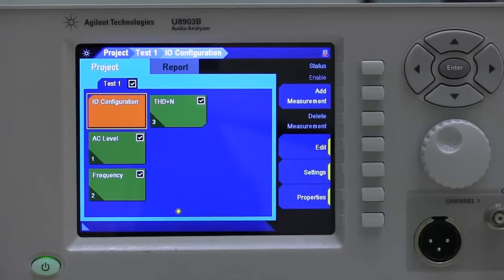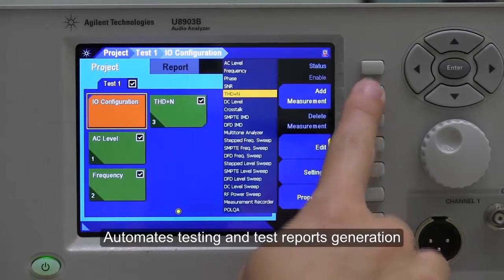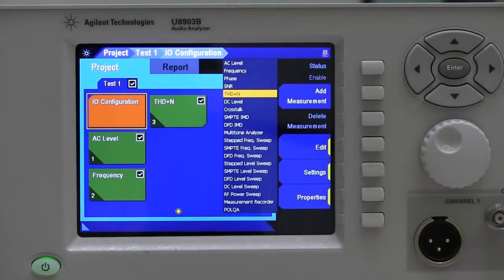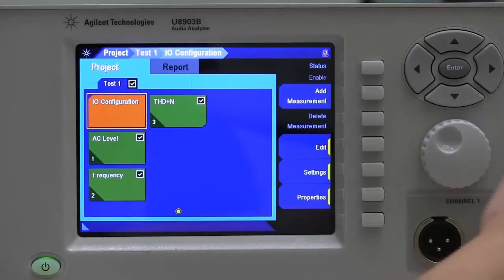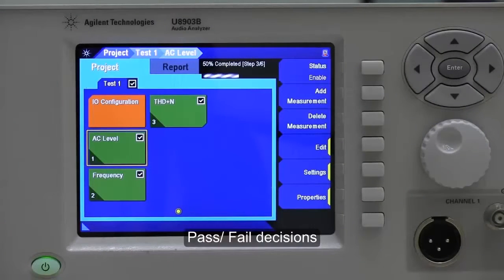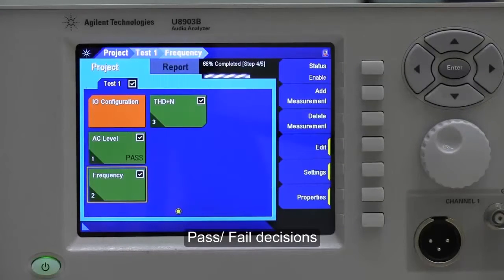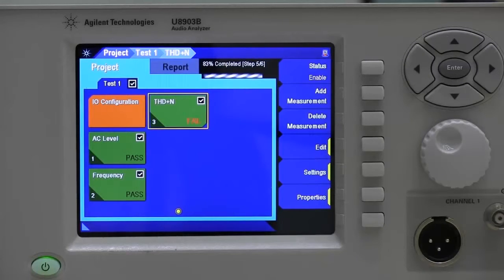This built-in test sequencer allows users to create flexible and easy-to-use test sequences that automate testing and provide test reports. This function removes the need to write complicated programming code or to purchase an additional external controller. Users can set up and define the types of measurements as well as define pass or fail decisions, reducing test development time as well as test time for the device under test.